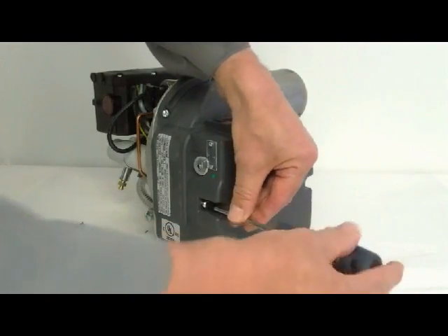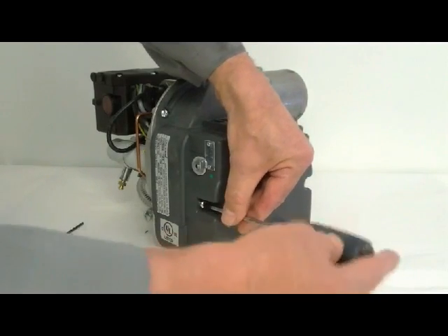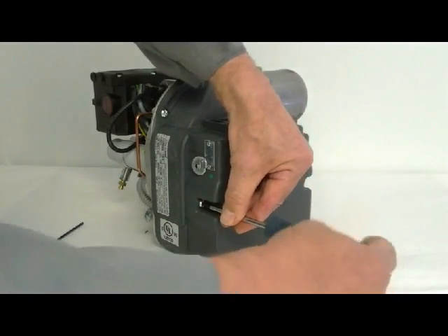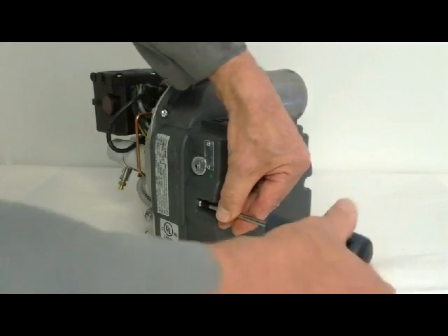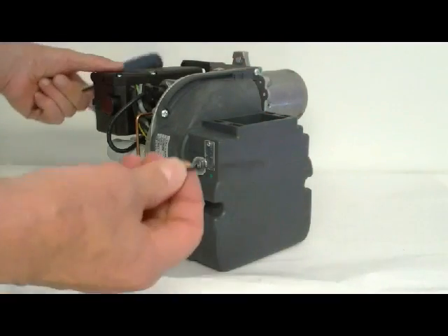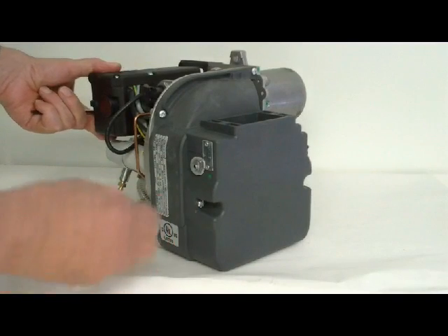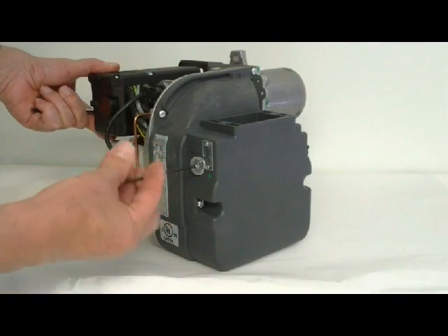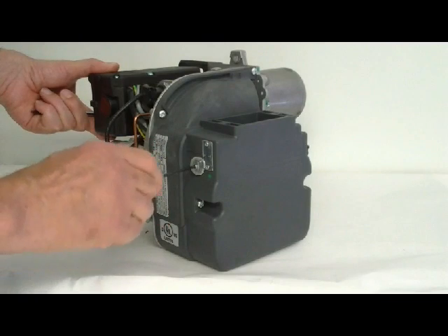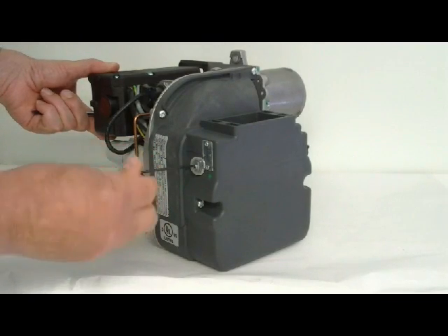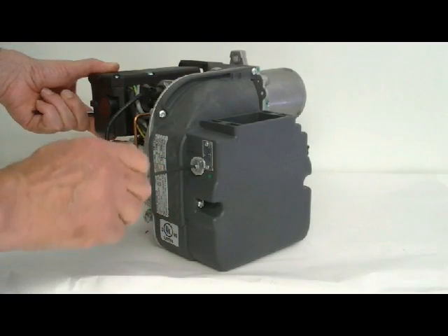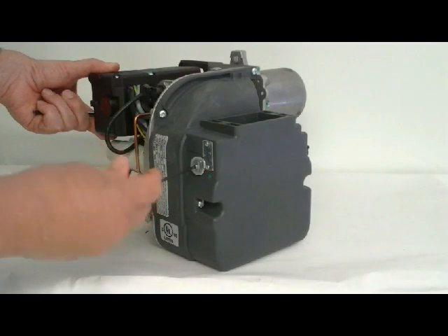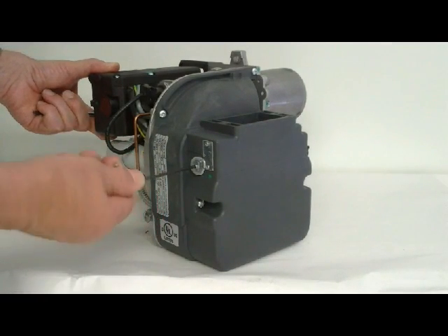The second air adjustment is made while the burner is in operation. Using a 3mm Allen wrench by adjusting the screw inside here, the damper internally is adjusted. This is for a fine adjustment of the air-fuel ratio to clean up combustion.